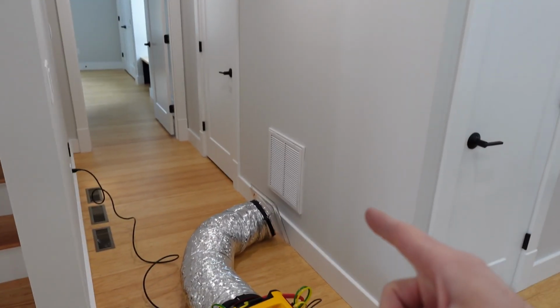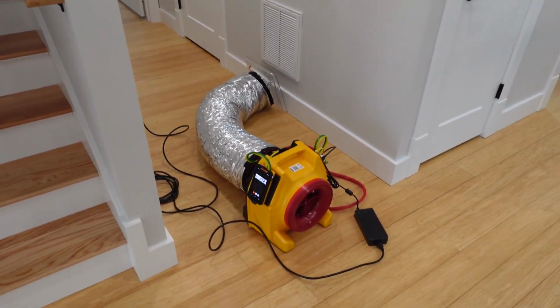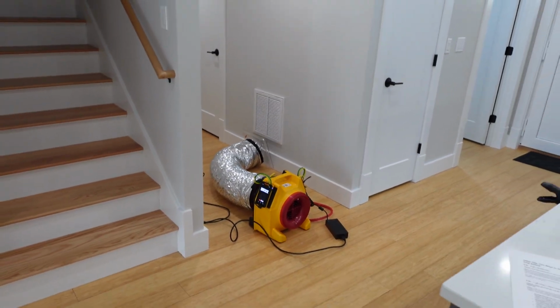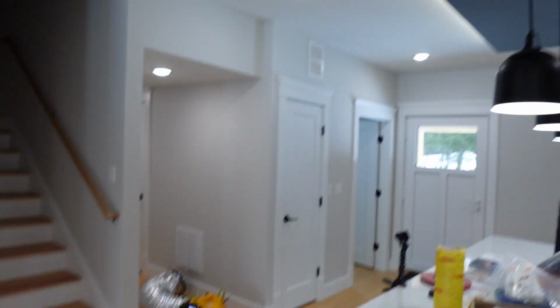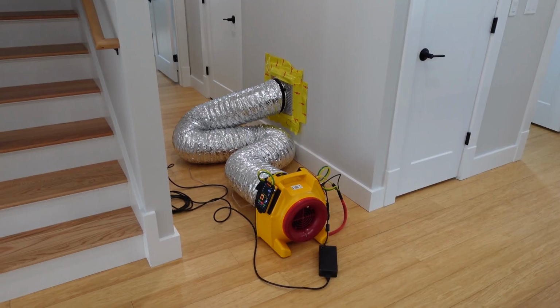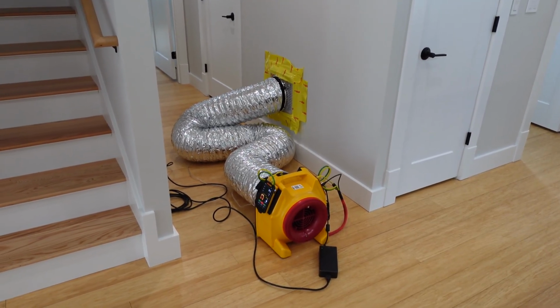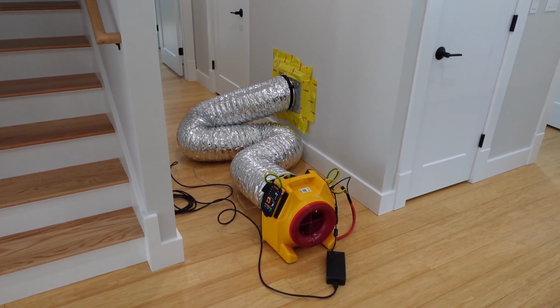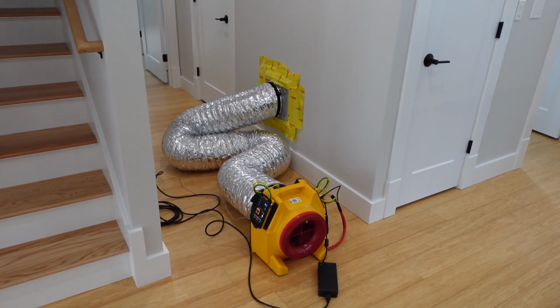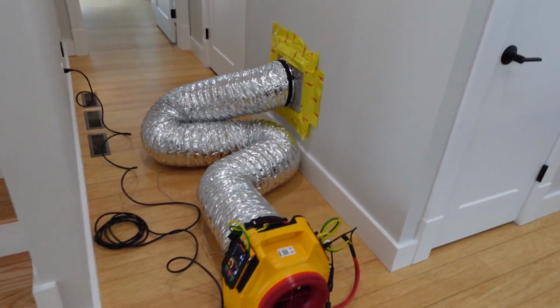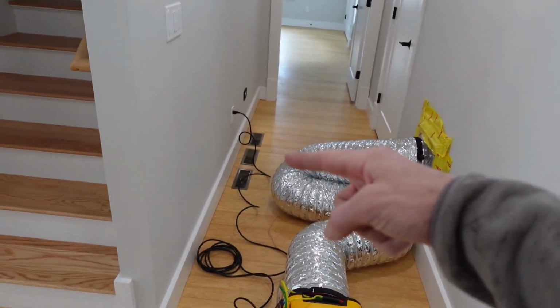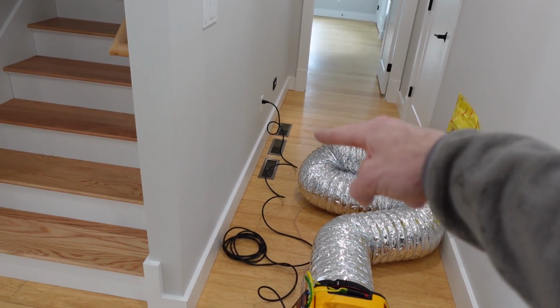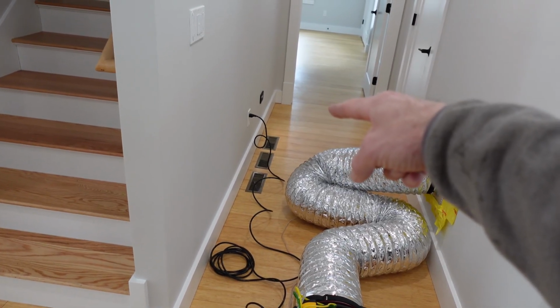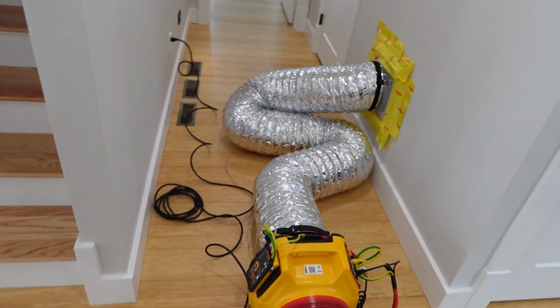So I'm going to get this hooked up, and we're going to do the total airflow test first, and then seal everything off and do a duct leakage test. All right, a couple reasons why I want to do a total system airflow test. One of them is I want to ensure the right amount of CFM is going in and out of this mixing hallway, so that I can better calculate when this puts out 100 CFM and that puts out 100 CFM, that I still have a negative pressure inside of this room.